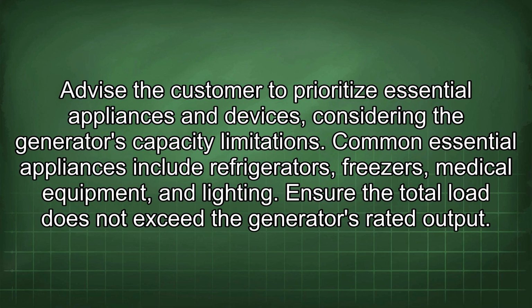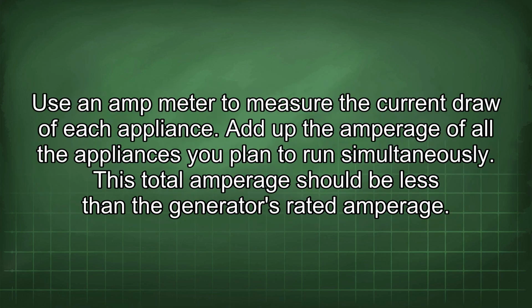Common essential appliances include refrigerators, freezers, medical equipment, and lighting. Ensure the total load does not exceed the generator's rated output. Use an amp meter to measure the current draw of each appliance. Add up the amperage of all the appliances you plan to run simultaneously.